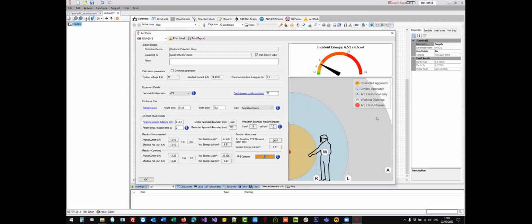A very important thing is that this diagram here that illustrates the boundaries, considering the restricted approach, the limited approach, the arc flash boundary, and the working distance are dynamically updated with any change in your parameters here. So for example, if I consider a closer distance for this person to work on this equipment, you see that the person will move closer to the incident of the arc flash, and of course, he's going to be exposed to a larger energy, leading the assessment to consider a larger PPE category.